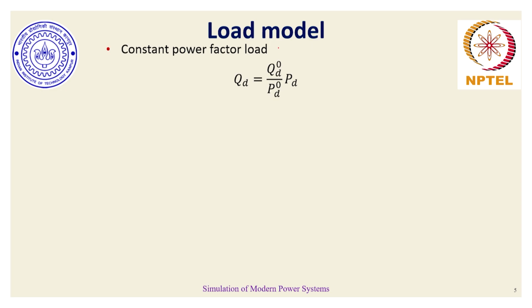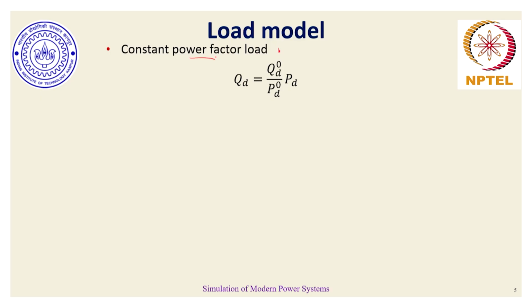So why is this a little more practical situation? Heavy industry loads, where there are different individual loads, when they have to project their power consumption at the grid level or at the aggregated level, the overall industrial load, having so many interior loads among themselves like pumping, lathing, soldering and so on, production systems, they tend to have these reactive power resources where, to avoid penalty from the grid side, the overall industrial load as an aggregated load can form an example of a constant power factor load.